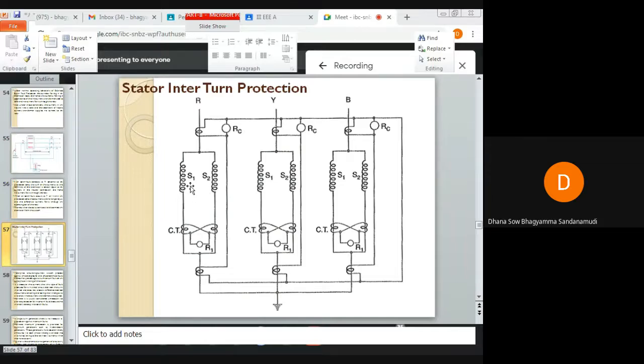So this winding is a double winding. In each phase there is a double winding: for R phase a double winding is there, for Y phase a double winding is there, and for B phase also a double winding is there. So if more than one winding is there in each phase, then interturn fault protection is required.